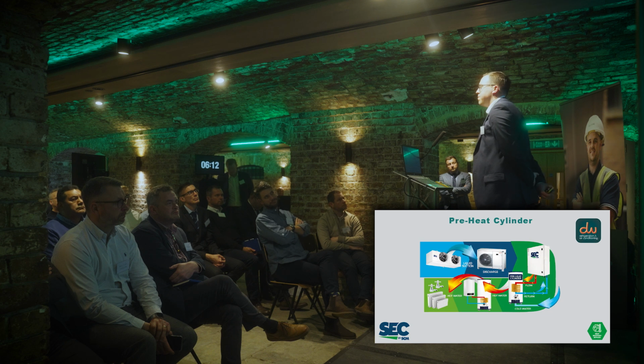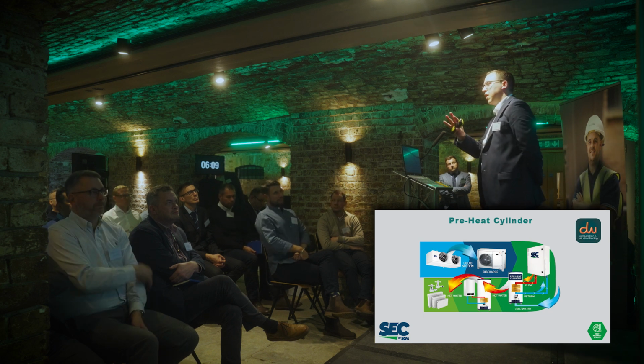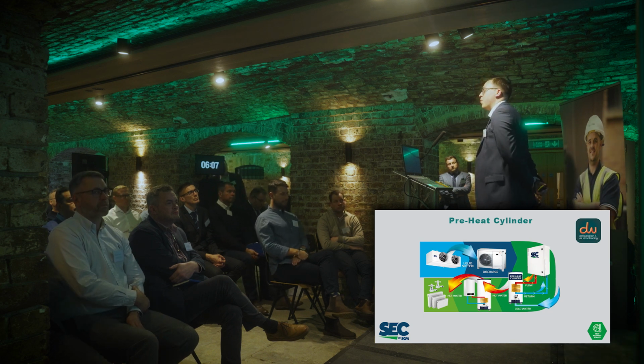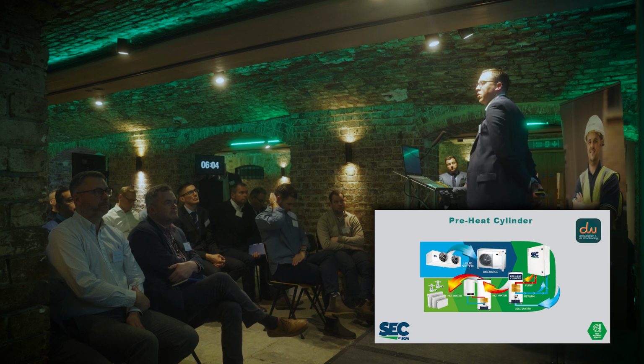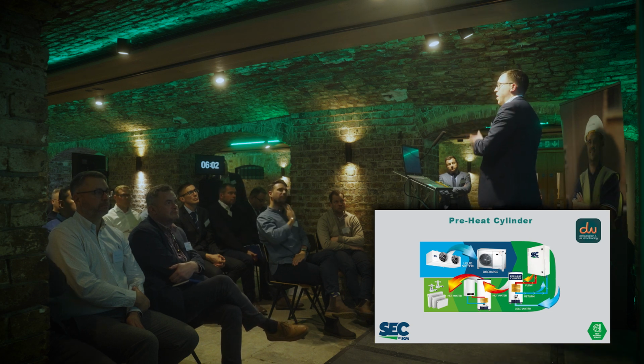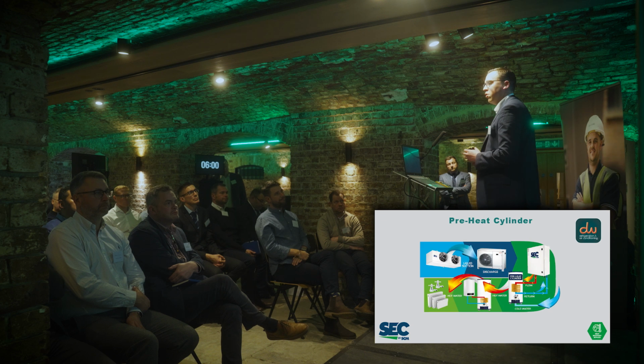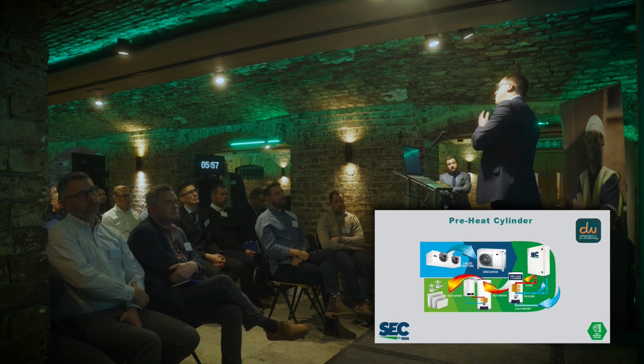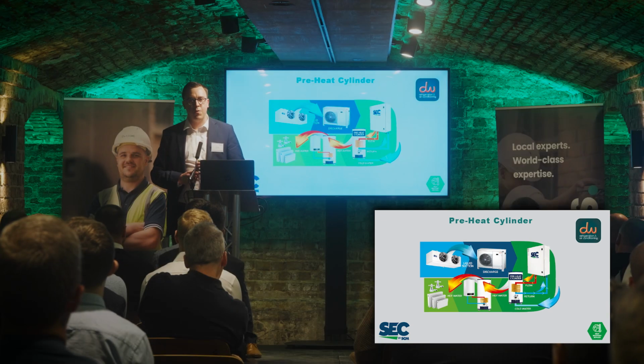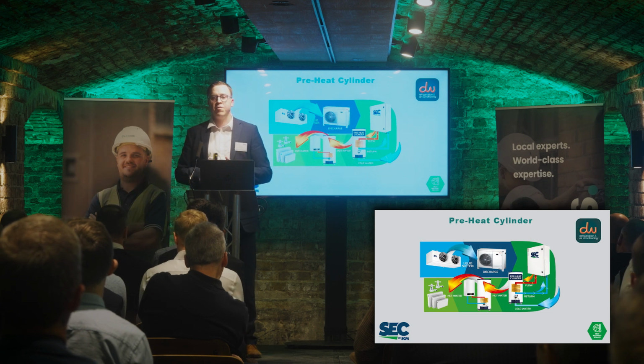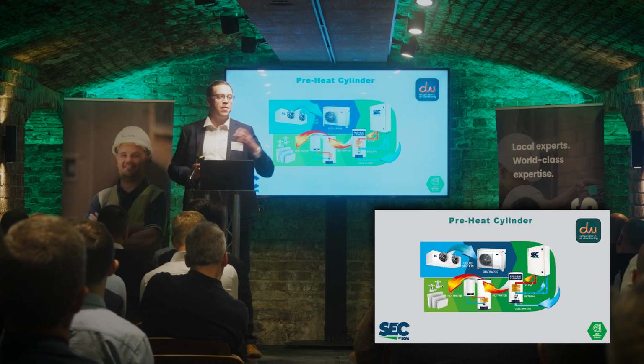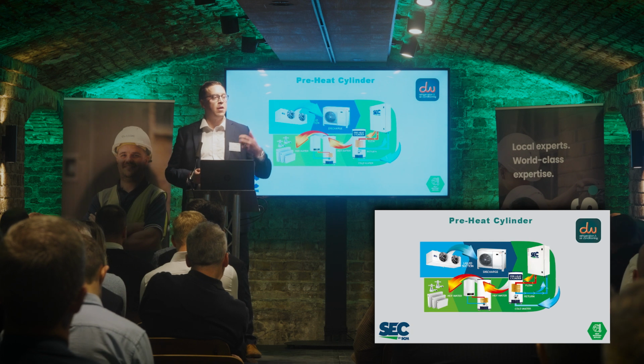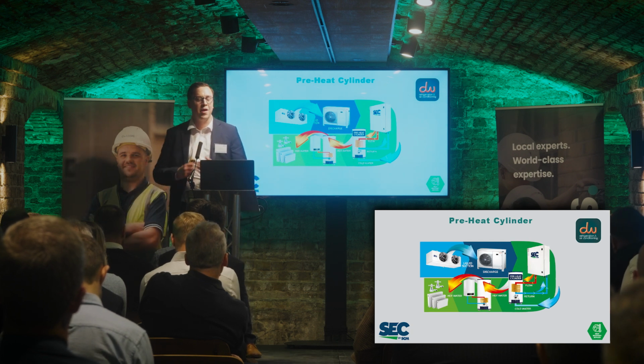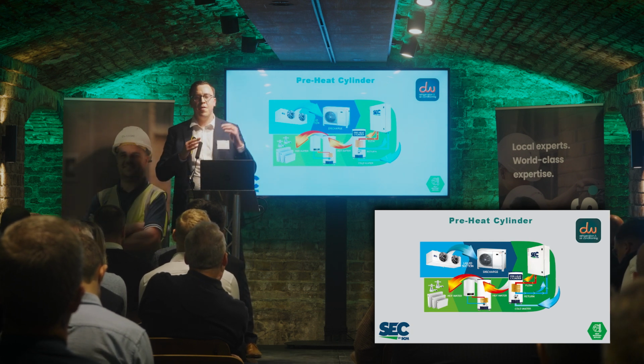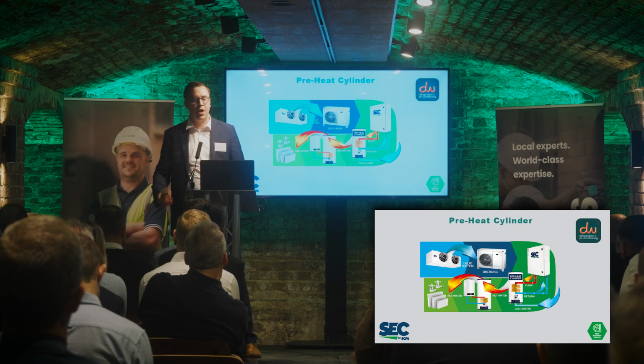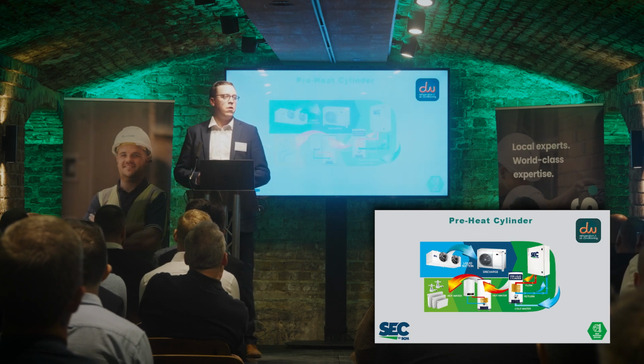We've got two main configurations that we use. Primarily the installations we've done of SEC are in what we call a preheat configuration. Your SEC panel is connected to your refrigeration side, your cooling side. We then deliver hot water, if it's the A1, A2L version, at around 50 degrees C into a tank. That tank then feeds the main hot water cylinder which has still got a gas boiler or electric immersion connected, and that will lift that water from 50 to 65 for Legionella and other bits and pieces.